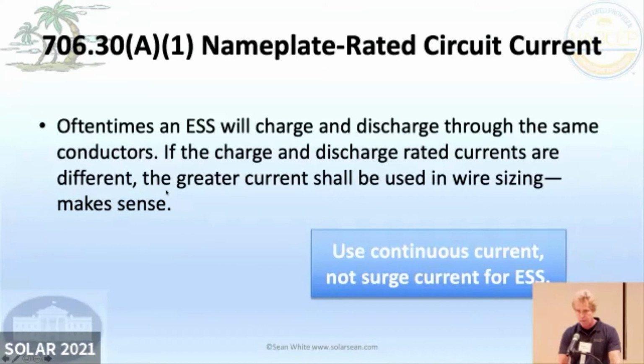With batteries too, like when you're working off grid, you need surge currents. You turn on a motor and it might use triple the current for half a second just to get that motor kicking. Let's say your motor uses 1 kilowatt, but all of a sudden it's 3 kilowatts just to get it kicking, and then it goes back to 1 kilowatt. Off-grid inverters can handle those surges, and oftentimes you have to read the label to see what it can do. But when you size the wires, you don't do it based on the surges. You do it based on the continuous current. Continuous means it can handle that current for 3 hours, because you size a wire for heat and things take a while to heat up, so that surge isn't going to cause it to get super hot.